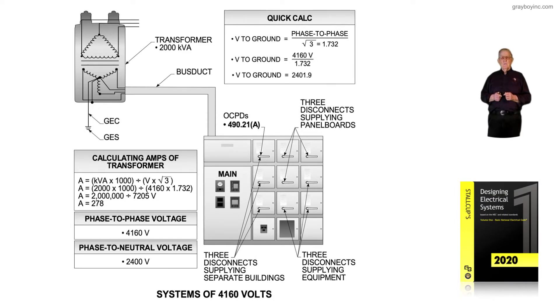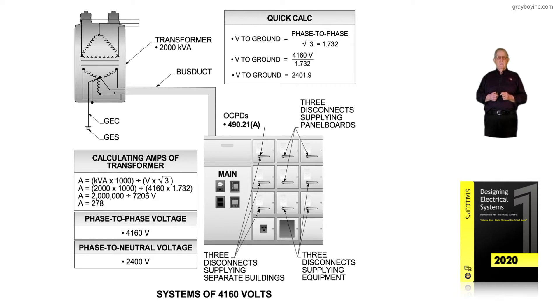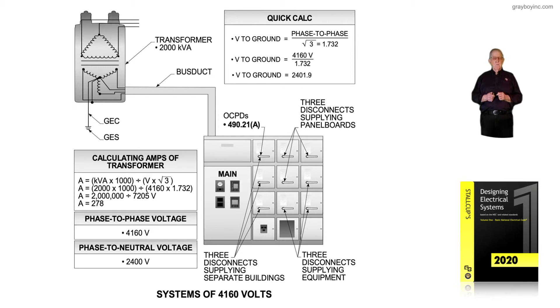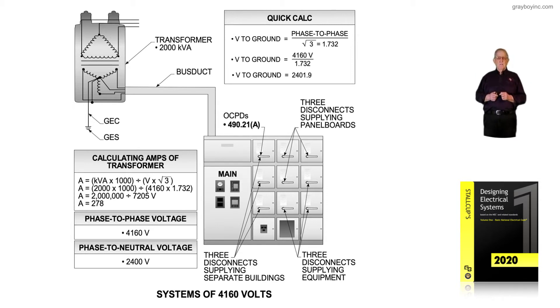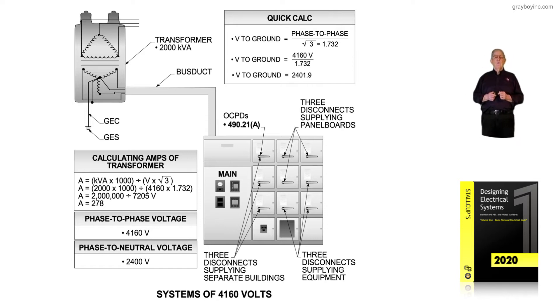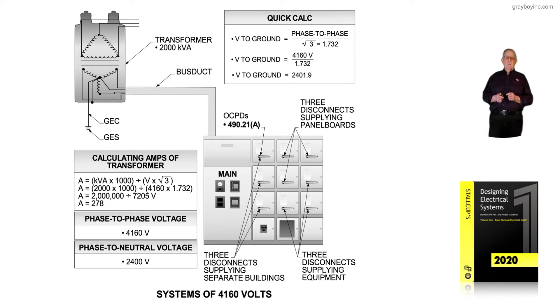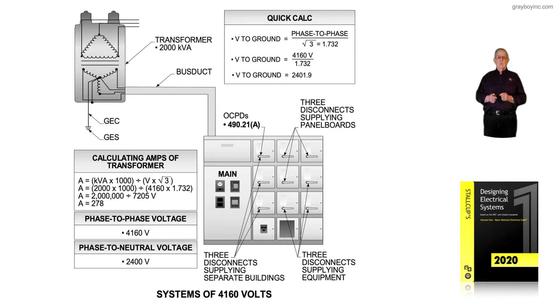This illustration deals with systems of 4160 volts. If we take 4160 volts divided by 1.732, we come up with a voltage to ground of 2400 volts — the voltage rating we're used to in our industry. This figure illustrates how many amps you would obtain using this voltage.